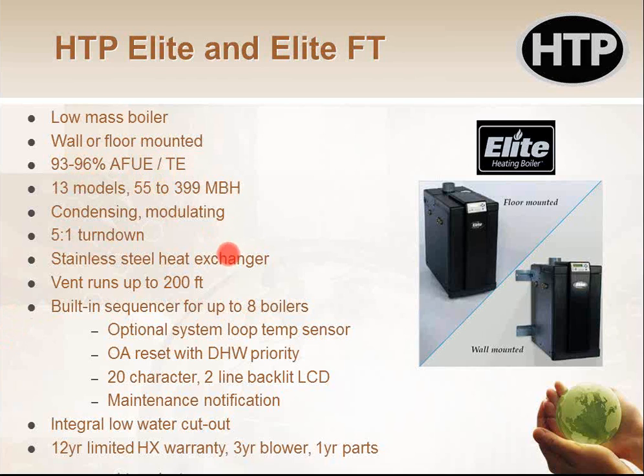Smaller boilers, 299 and less, are rated in AFUE, annual fuel utilization efficiency. Larger boilers from all manufacturers, 300,000 BTUs and up, are rated in thermal efficiency. So those two are not interchangeable, but they're fairly close, within 1% or so. This one has a 5-to-1 turn down, which means it can modulate from 20 to 100%. It has the same heat exchanger as that little one I just showed you. It's a stainless steel low mass heat exchanger, and it's got a pretty beefy exhaust fan, so it can vent up to about 200 feet, which should cover you for most situations.